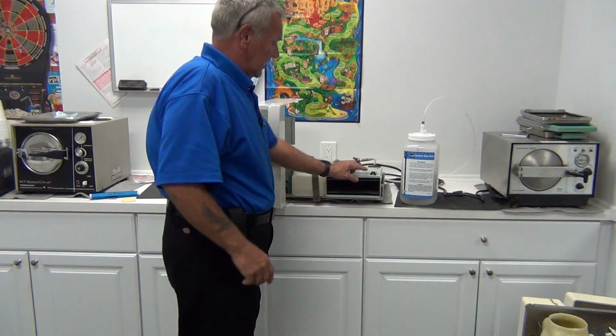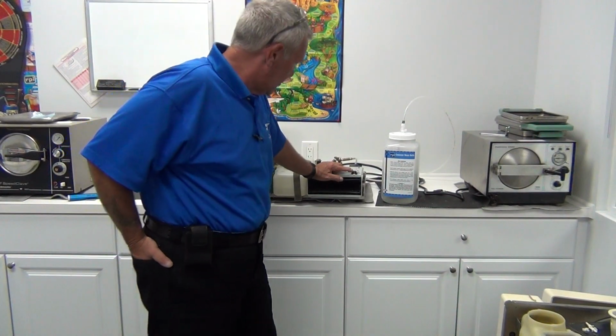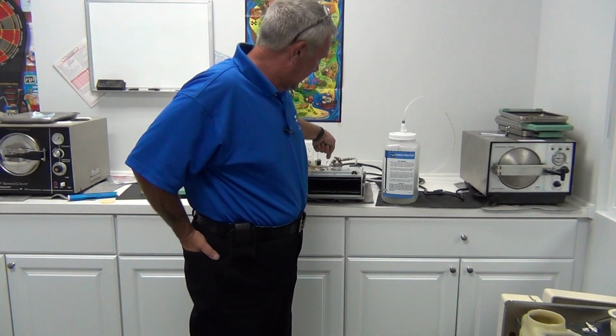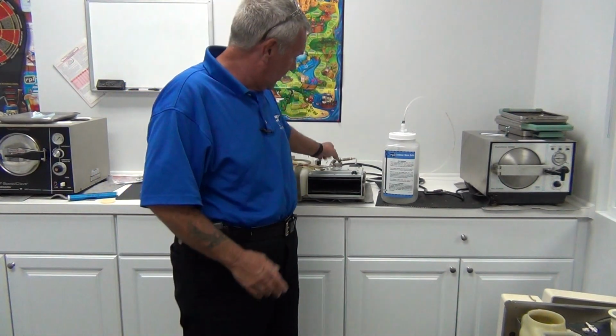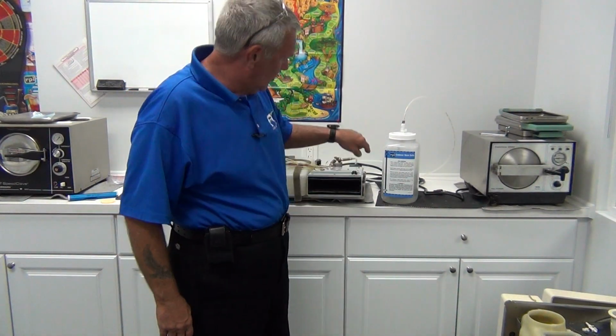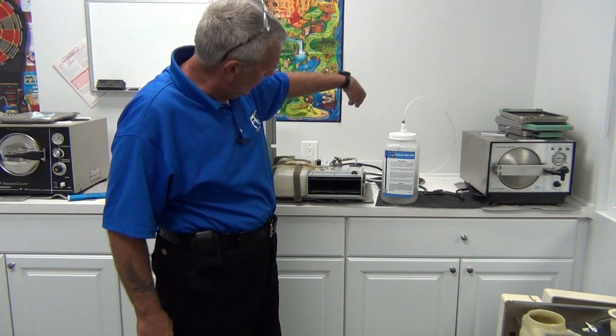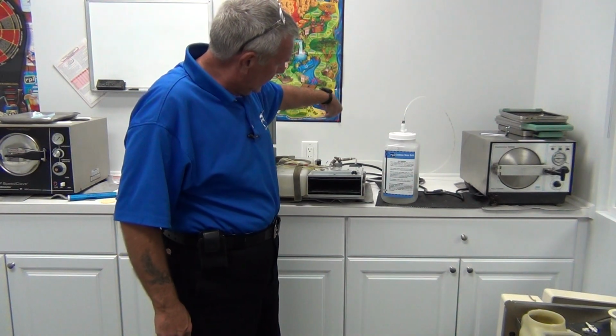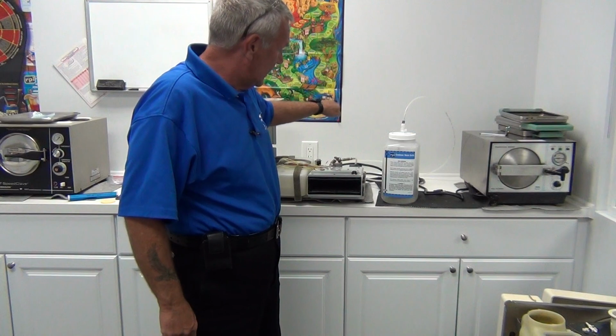Next, we're going to check the level. We have a bead here that's level. It should be slightly off level, believe it or not. As the cassette leaks, there's a drain hole in the back of the cassette chamber that collects the condensation, the leak, and turns it back into water and dumps it on the counter. So you want it to run slightly downhill to the left and downhill to the left rear. Slightly, about half a bead.